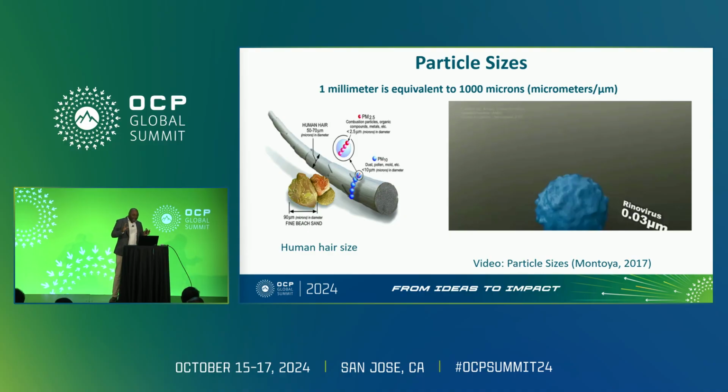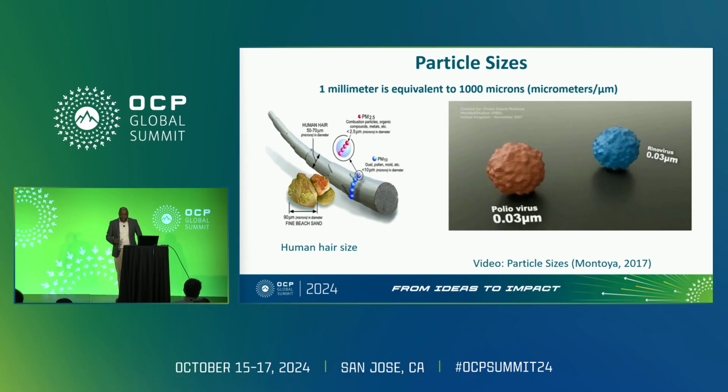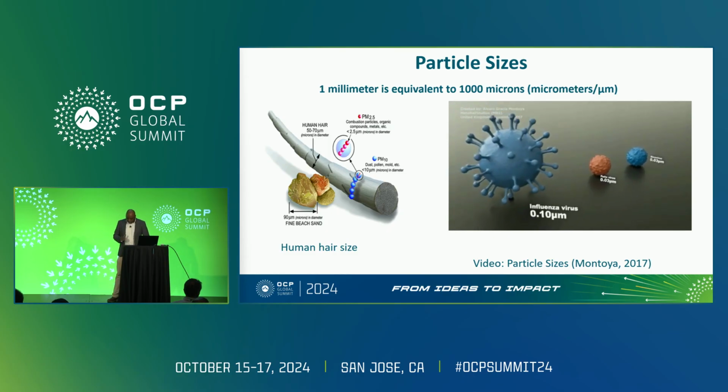Some of them are relatively easy to remove, so hard particles like rust, sand, carbon. They would typically remain trapped in the filter throughout the lifetime of the filter. Other particulates, such as fibers, gels, colloids, are typically a bit more difficult to remove and can unload if the pressure increases. I want to share a video that gives a good visual indicator of the type of particles that we're looking at size-wise.